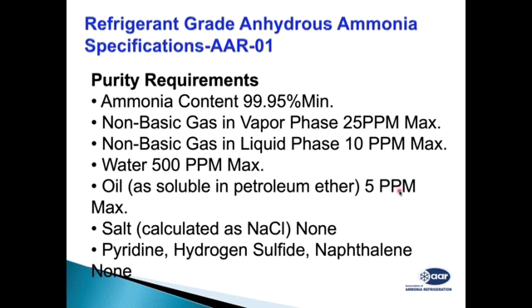So this ammonia, which we are talking about today, for our ammonia refrigeration system, we need a pure ammonia. Pure ammonia means it should be 99.95% pure ammonia. Normally, when we buy ammonia from the market, we do not get a certificate of purity. It comes in cylinders, and many times we don't know what is the purity of the ammonia received.